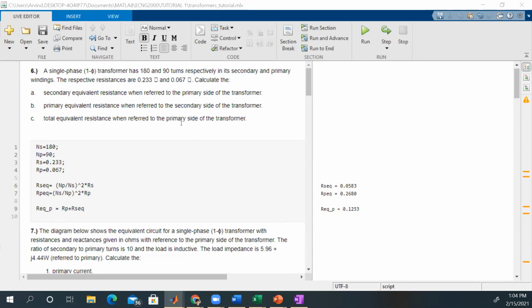So here we have to calculate the secondary equivalent resistance when referred to the primary side. This is just referring parameters, and we know the resistances scale with the square of the turns ratio. Going from secondary to primary: R secondary equivalent equals (NP/NS) squared multiplied by RS, which gives us 0.0583.